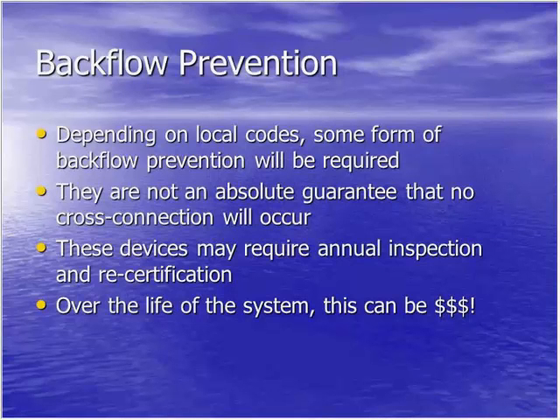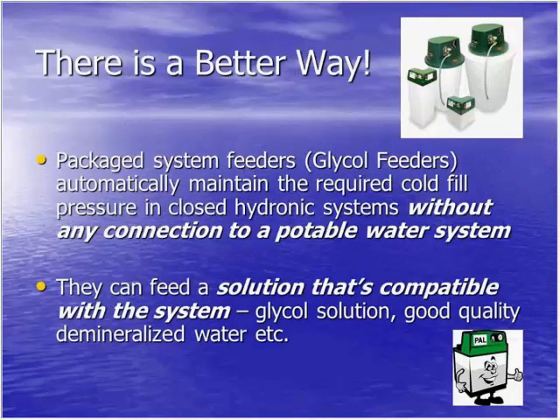So there is a better way, and that's to use a package system feeder. The industry also calls them glycol feeders. I like to call them package system feeders because I like to promote them for use on systems that require just water. They automatically maintain the required cold fill pressure in closed hydronic systems without any connection to a potable water system. They can feed a solution that's compatible with the system, a glycol solution, good quality demineralized water, or anything else.